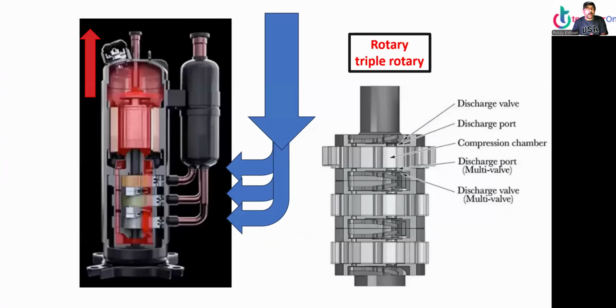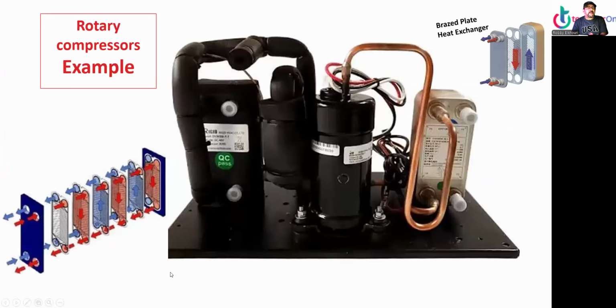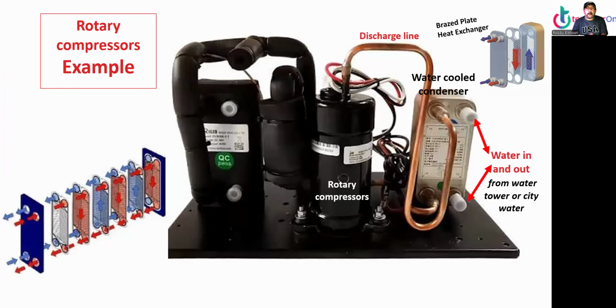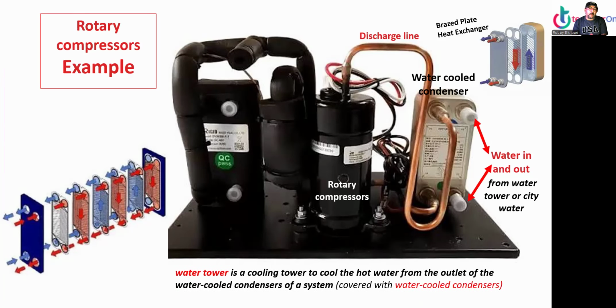Next slide. Okay, so now we have the triple rotary. This is an example of a rotary compressor, because it's small: rotary compressor, discharge line, water-cooled condenser. This is water in and out from the water tower or city water. We have a water tower that cools the water. The water tower is a cooling tower to cool the hot water from the outlet of the water-cooled condenser of the system. I cover it in the condenser section. I'll cover it later, I have pictures of it later.